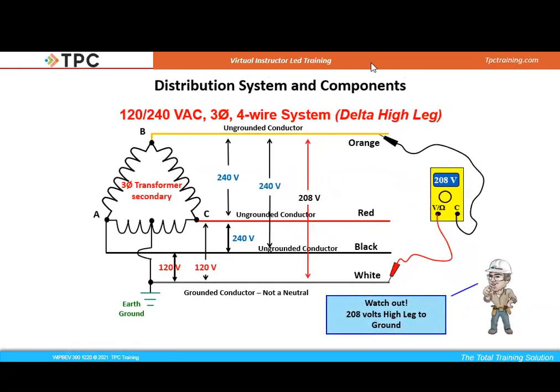And so this is what they call a high leg delta. And I wanted to show you this because it is three transformers again. So there's no doubt about it that I do have a three phase system here. But we configured the transformers not in a Y, but in a triangular configuration. And we call that a delta. And this delta is not one to take lightly either, because notice it says high leg.